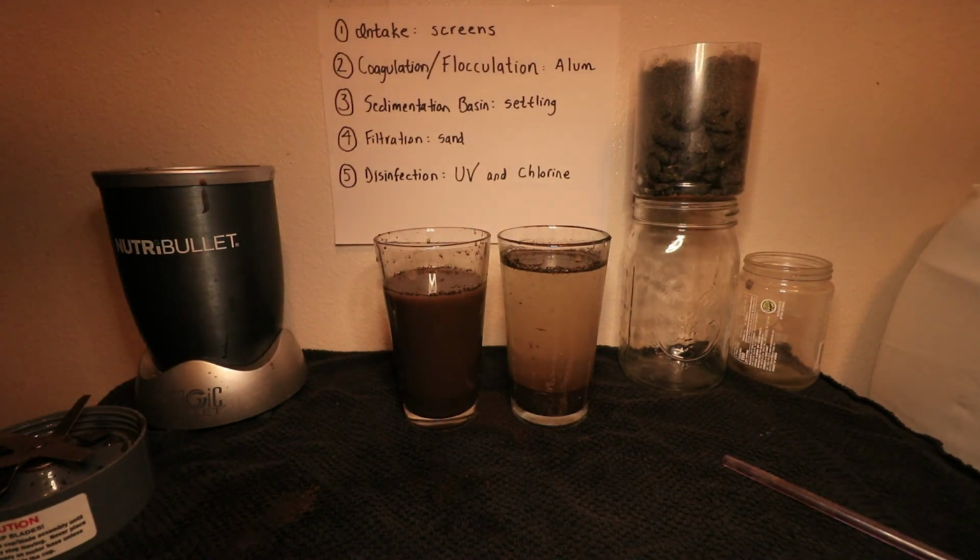In a drinking water treatment facility, this will oftentimes be in a number of basins that the water slowly flows from one to the next to give time for the particles to really settle out. The settling velocity is what's important here. It needs to happen faster than the water makes its way from the inlet of the settling basins to the outlet of the settling basins. And after the sedimentation settling process comes the filtration process.